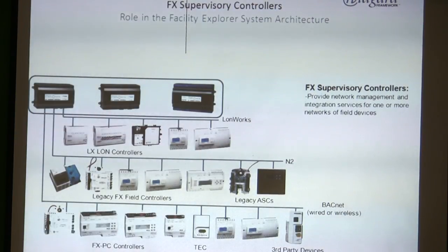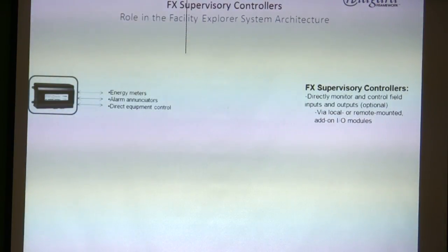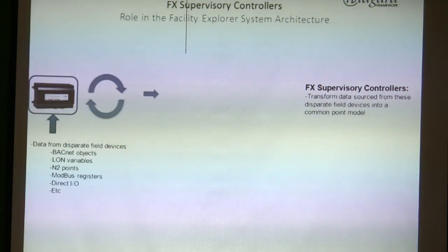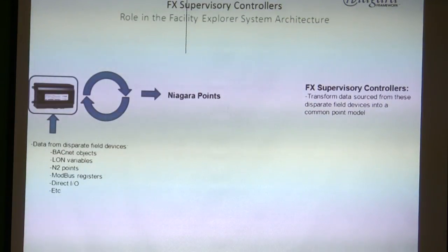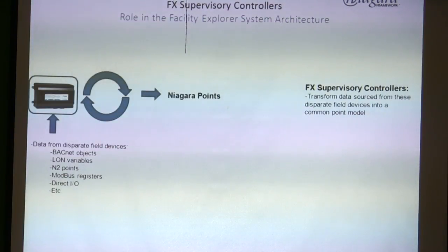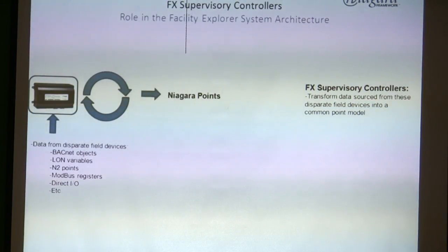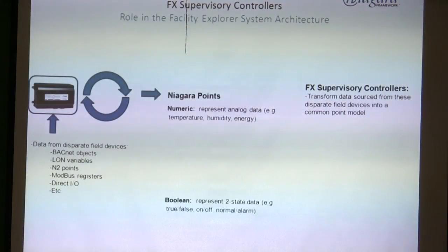There are a gazillion different things you can do. These controllers are all talking Modbus, BACnet, and LonWorks — we're sucking all of these up into a Jace and doing something called normalizing them. The Jace turns those into Niagara points. Niagara is the computer system owned by Tridium that the Jace uses to program and set everything up.